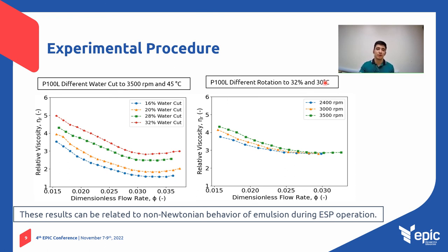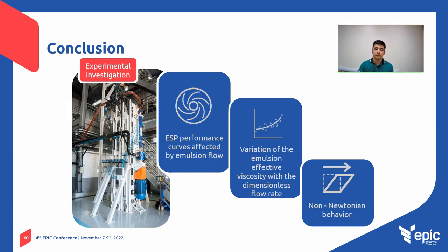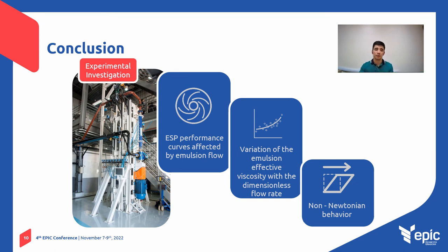The decrease of these parameters refers to flow rate reduction or increase of ESP rotational speed. An ESP performance analysis was carried out operating with unstable water-oil emulsion. A viscous head degradation was exacerbated due to the effective viscosity of the emulsion, and non-Newtonian behavior was evidenced within the ESP.